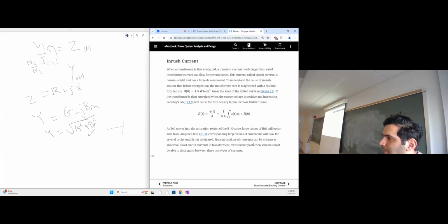The second issue is the inrush current. So basically, when the transformer first gets energized, it's not a linear circuit. Okay. So it will experience a very high starting current circulating in the magnet itself or in the equipment. And that value could be several times the rated value. It could be, let's say, 5,000, 6,000 in comparison with 1,000, I'm just using some units here. So it could be 5, 6 times the rated values. So from the transformer side, that raises a lot of tension. And there are a number of protection schemes to make sure that our transformer will not get damaged at the starting. Okay? So it should have certain capability or strength to avoid the breakdown. So this is the issue with the inrush current. Hopefully the transformer will be able to get energized, and then we'll reach a stable operation after a few cycles. But this is something to consider.